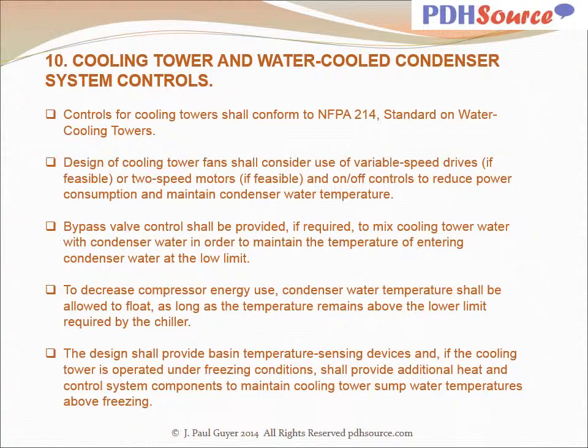To decrease compressor energy use, condenser water temperature shall be allowed to float as long as the temperature remains above the lower limit required by the chiller. The design shall provide basin temperature sensing devices, and if the cooling tower is operated under freezing conditions, shall provide additional heat and control system components to maintain cooling tower sump water temperatures above freezing.